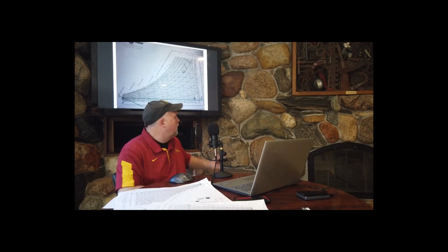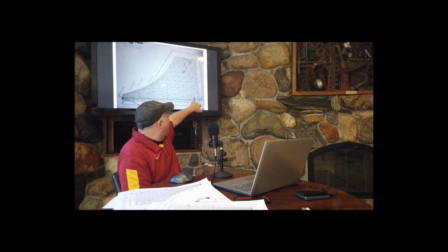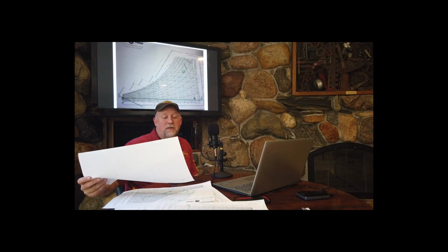Okay, and then I did the same thing all the way down at 30 degrees Fahrenheit, 50% relative humidity. The enthalpy is about 9 BTU per pound. Take this all the way out here. It's only 12 grains of moisture and a dew point of 15 degrees. Any condensation, well, obviously will come as frost.